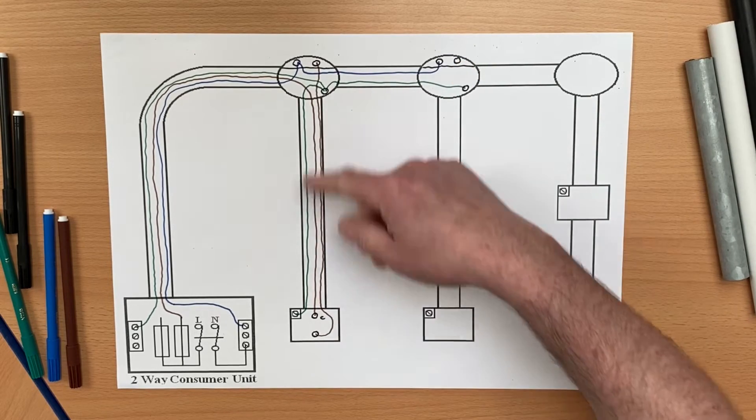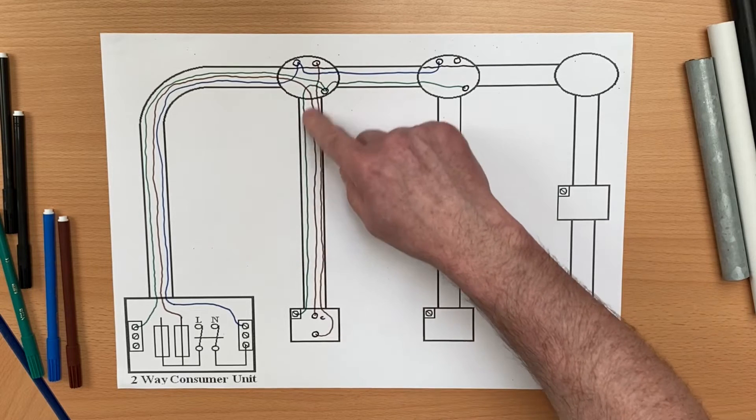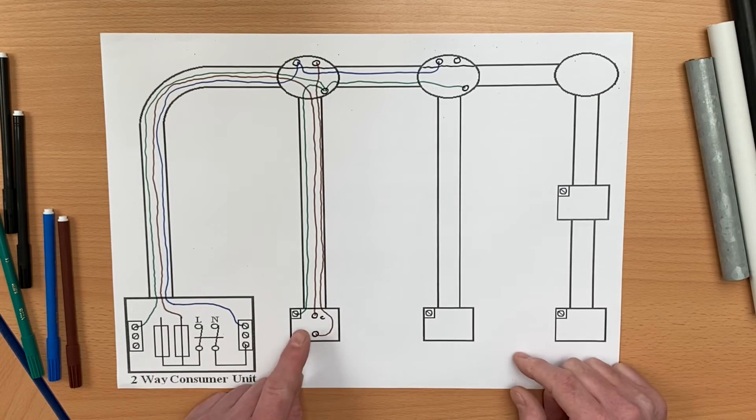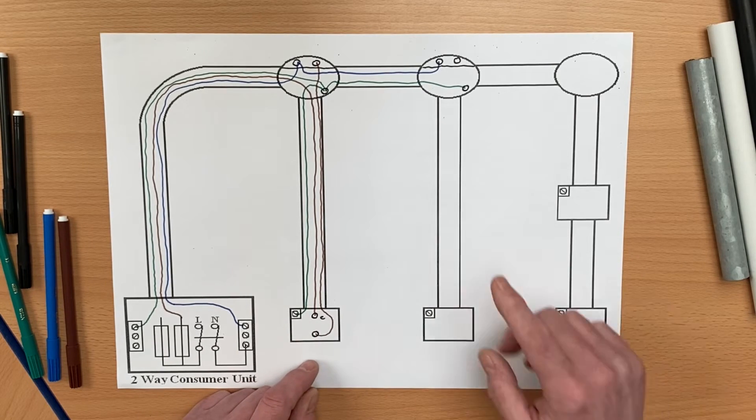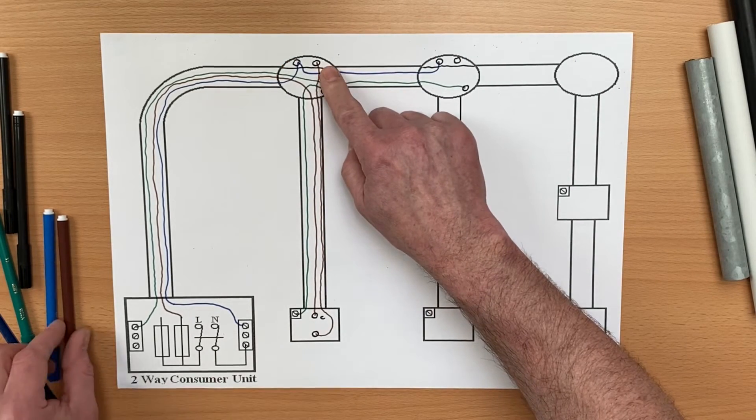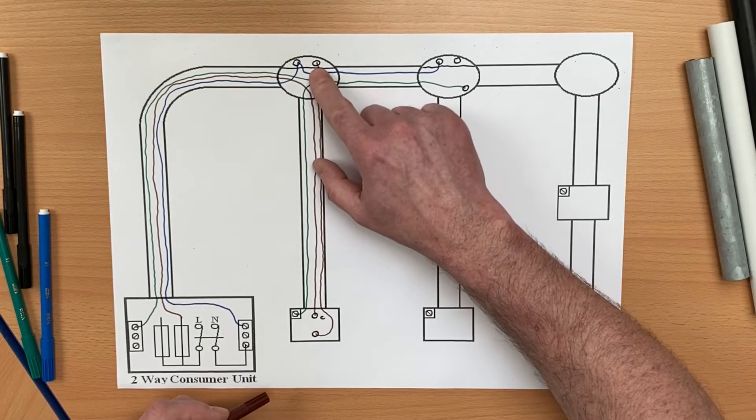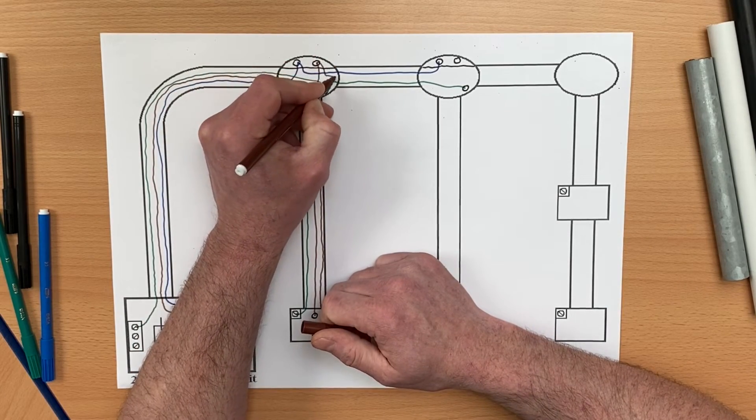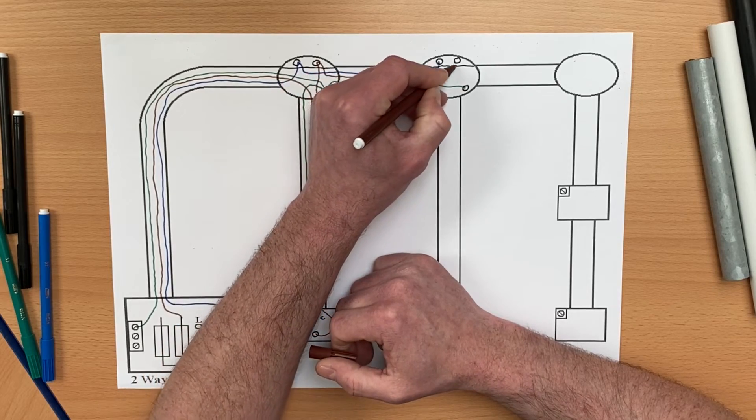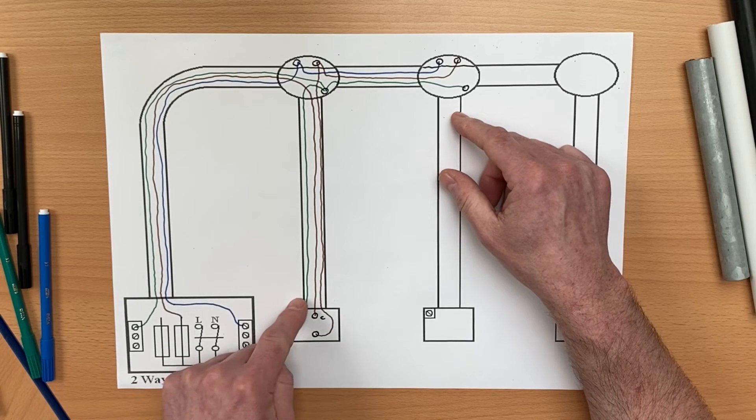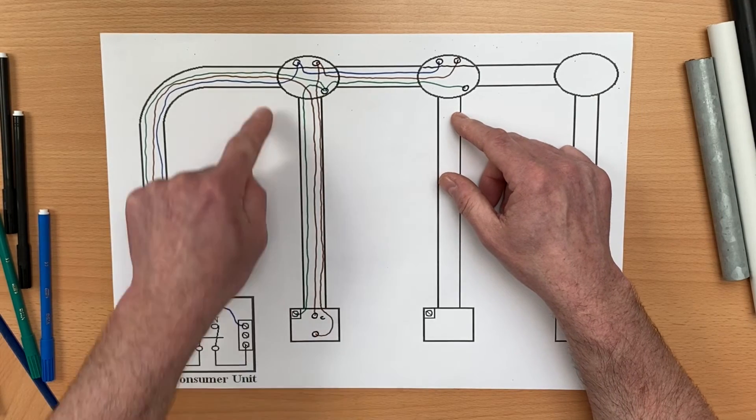However, this might be a 10 meter drop, might be some distance away, and that is not the closest switching line of this part of the circuit. Have a think—where would the closest switching line be to make this light and this light come on together? Well it's here, isn't it? It's just here. This switching line conductor here turns on this light. If we were to extend it through into here, into the next area, the next lighting point in the office.